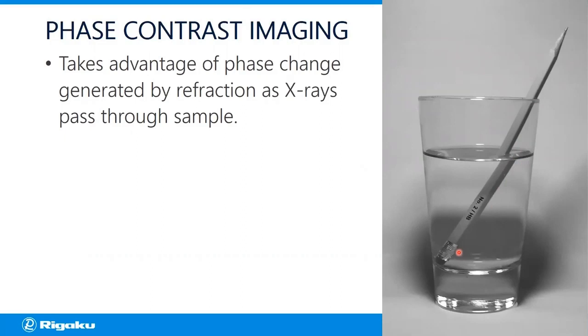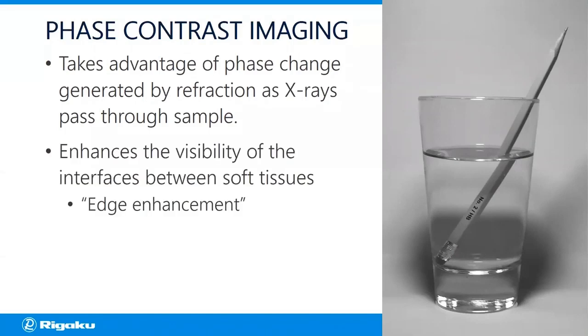Phase contrast is primarily used when imaging materials that have low absorption, like biological materials, because we want contrast enhancement. Systems that use this require additional hardware — gratings or slits upstream and downstream of the sample — to help measure the subtle changes in intensity induced by refraction. Phase contrast imaging is really sensitive to transitions between different materials or borders, helping us differentiate between materials of similar density, such as neighboring organs. It's often referred to as an edge enhancement technique.